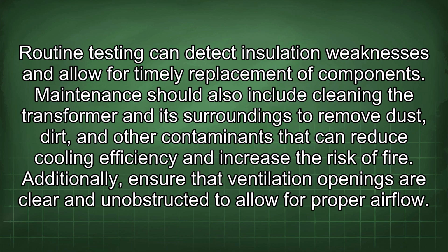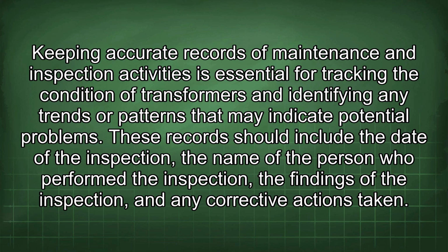Maintenance should also include cleaning the transformer and its surroundings to remove dust, dirt, and other contaminants that can reduce cooling efficiency and increase the risk of fire. Additionally, ensure that ventilation openings are clear and unobstructed to allow for proper airflow. Keeping accurate records of maintenance and inspection activities is essential for tracking the condition of transformers and identifying any trends or patterns that may indicate potential problems.